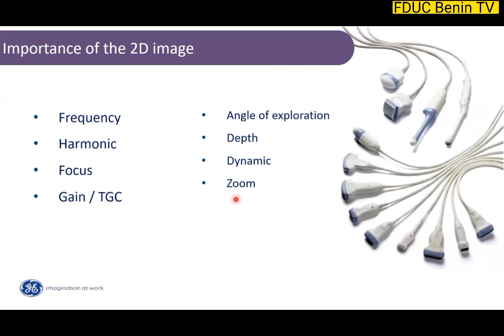The focal zone is the narrowest portion of the ultrasound beam in the tissue. At this point, it's the point where the emitted beam will give us the best spatial resolution. So if you see here, first of all, in this 2D image, if you can see really here, we are moving our focus position up and down.